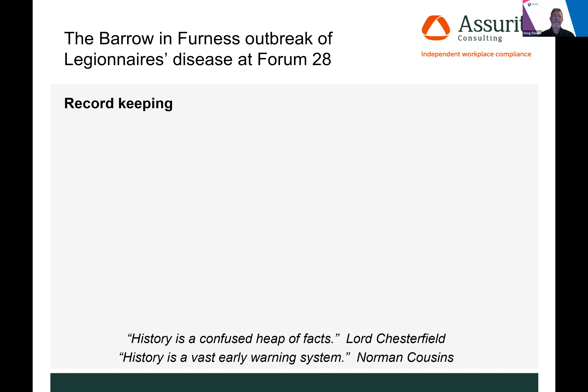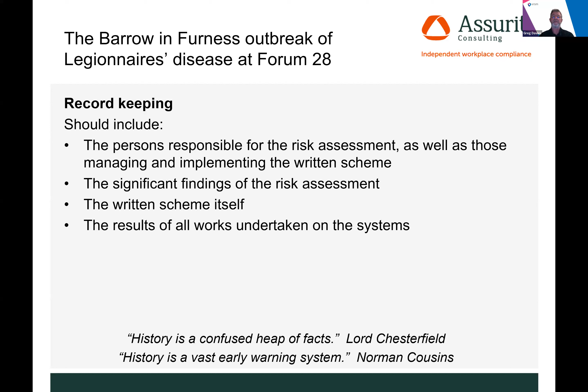So what did this look like for the case in question, in terms of what record keeping was required? L8 is very specific on this, and these are pretty much the requirements: you need a good idea of what the management looks like, the significant findings in reality, the risk assessment, what the written scheme looks like, and the results of all work undertaken on the system. As a reminder, the top three elements L8 advises you keep for a minimum of 2 years. The results of all work, so testing, inspecting, and monitoring carried out on the system, the expectation is 5 years' worth of retrospective data to be able to go back and look through.